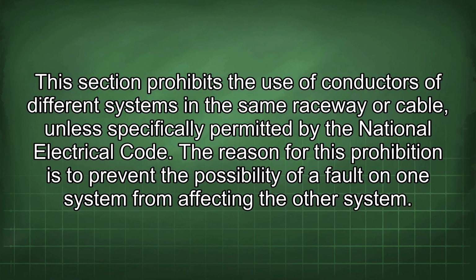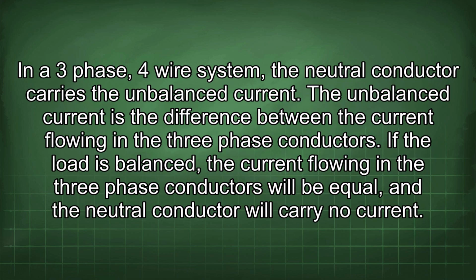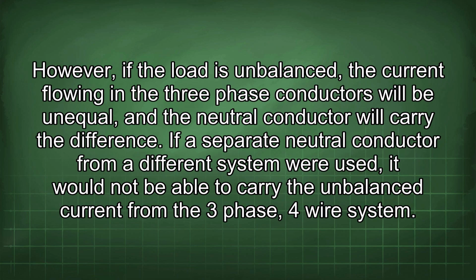The reason for this prohibition is to prevent the possibility of a fault on one system from affecting the other system. In a 3-phase 4-wire system, the neutral conductor carries the unbalanced current. The unbalanced current is the difference between the current flowing in the 3 phase conductors. If the load is balanced, the current flowing in the 3 phase conductors will be equal and the neutral conductor will carry no current. However, if the load is unbalanced, the current flowing in the 3 phase conductors will be unequal and the neutral conductor will carry the difference.